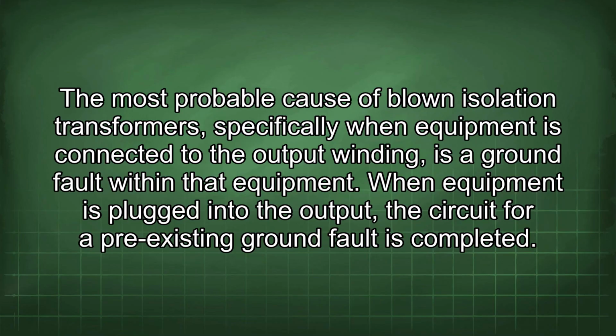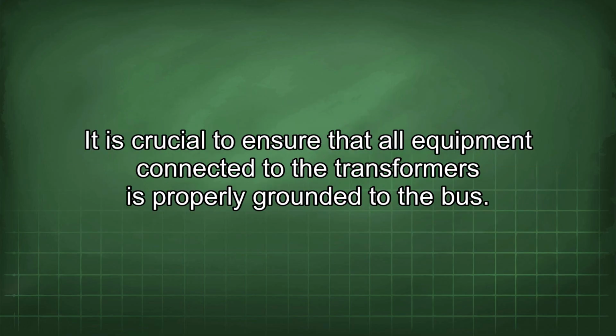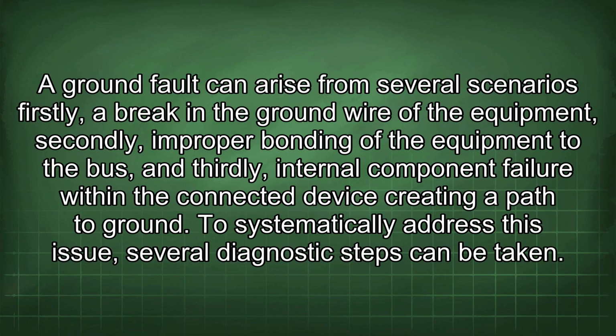The most probable cause of blown isolation transformers, specifically when equipment is connected to the output winding, is a ground fault within that equipment. When equipment is plugged into the output, the circuit for a pre-existing ground fault is completed. It is crucial to ensure that all equipment connected to the transformers is properly grounded to the bus. A ground fault can arise from several scenarios.